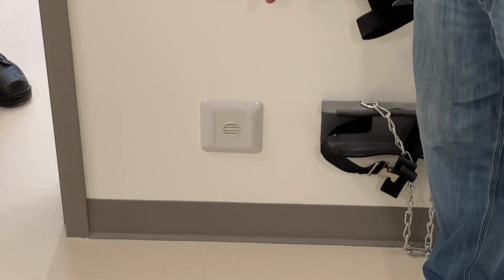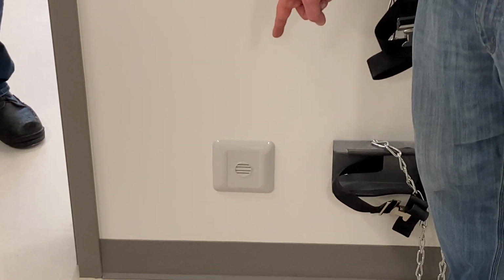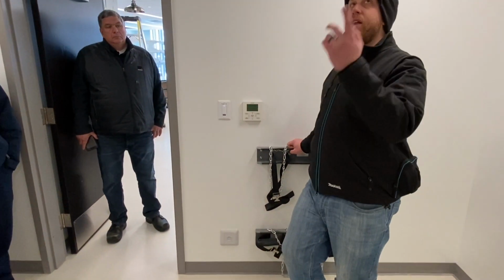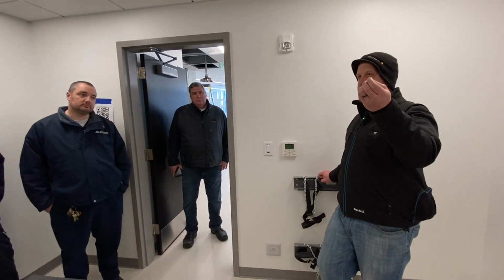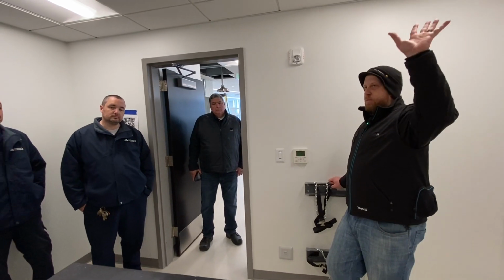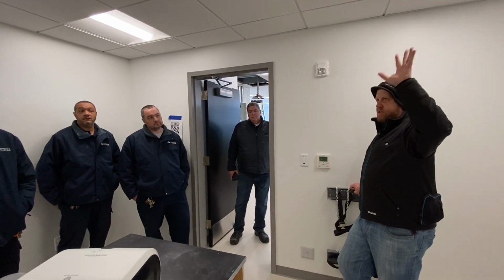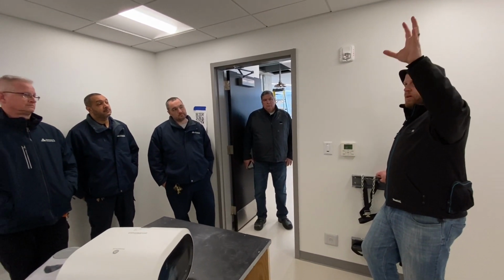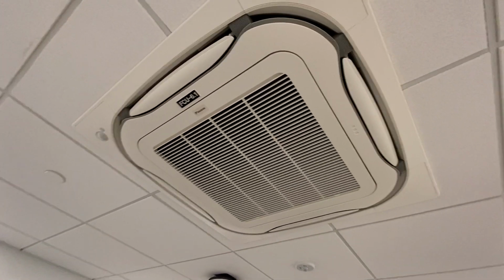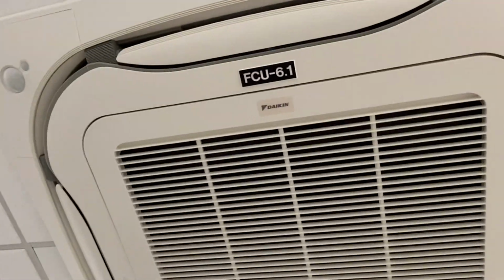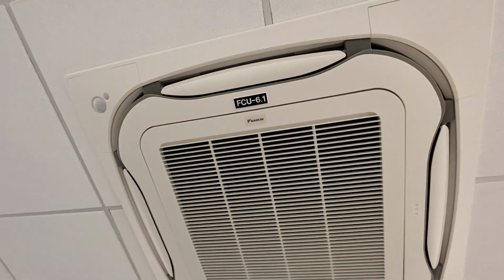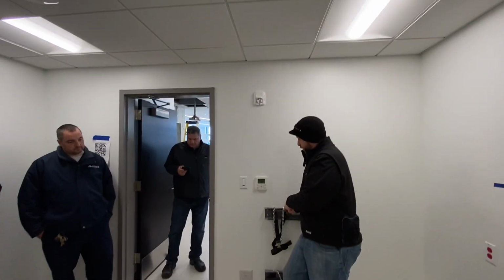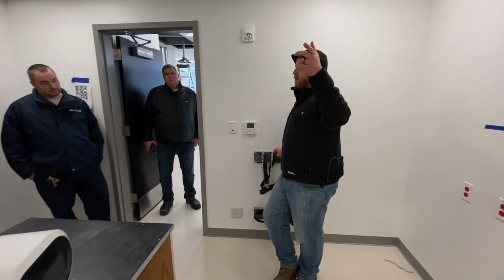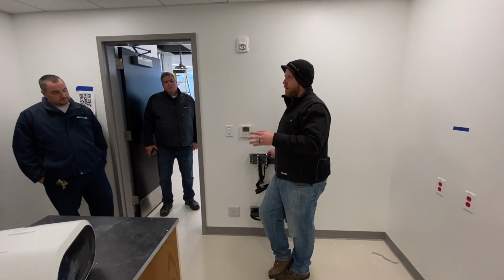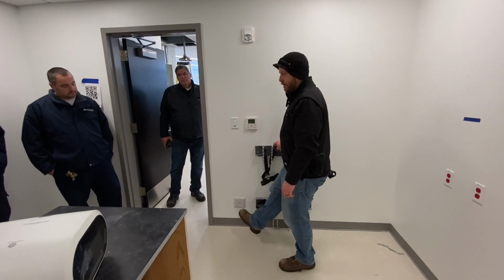This guy down here is an R410A refrigerant monitor sniffer. The intent is that if one of these things were to get a leaky connection or something and all of a sudden start dumping refrigerant - remember there's only 6 compressors. Did you guys get the Daikin training yet? Okay, so there's 6 compressors on the thing. The idea is that all that refrigerant dumps into this one small space, you could have a bad situation. So it's designed so that this catches it, and there are isolation valves on the refrigerant to close. What happens is this detects refrigerant, we isolate the refrigerant lines, shut down the entire system, and send an alarm to the BMS. So there's its own sequence just for monitoring that.